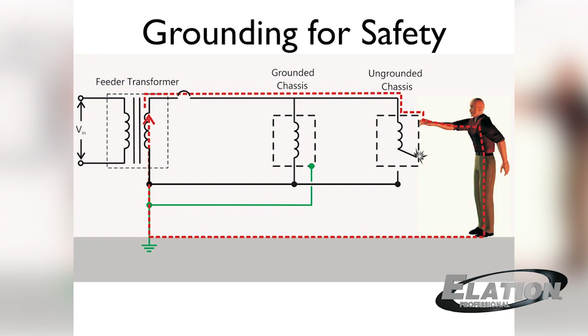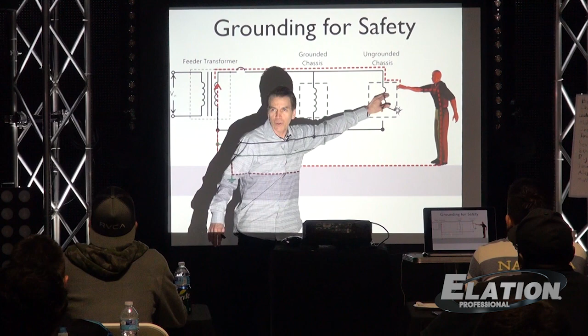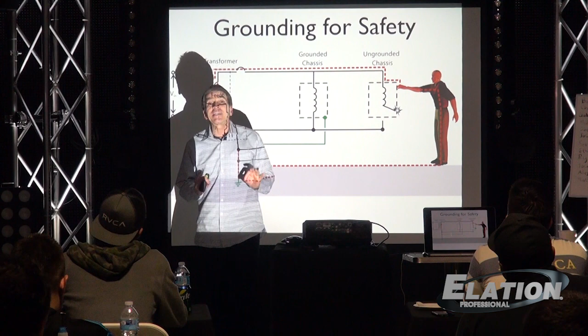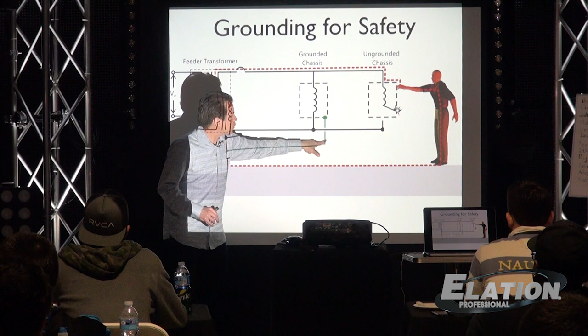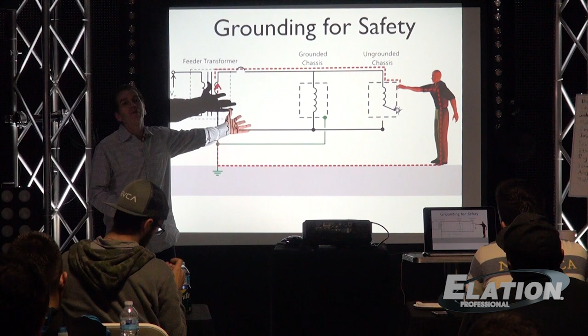This could be a damaged grounding conductor, a lifted ground, or it could just be wired wrong. So if there's a fault, meaning a short circuit to the case, and somebody touches it, there's a path for fault current that goes through the metal chassis, through the person, through the earth, back to the supply. If there's a fault on the other piece of gear, the path for fault current goes through the green grounding conductor, and it trips the circuit breaker and opens it up. We already talked about all that. So that's how important the green grounding conductor is, and every piece of metal needs to be connected to one, for that very reason.